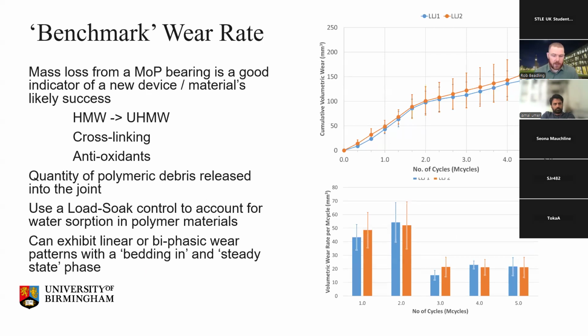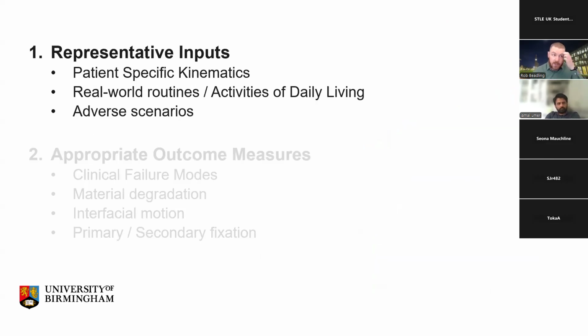And then we see a lot of failure modes that aren't captured in that testing, and then a lot of research goes into trying to understand why that failure happened, as opposed to doing it the other way, where you do the safety or the representative testing to make sure the device is safe beforehand, before it's then implanted into people. So the bulk of my research has been around improving preclinical testing, and that's been through 2 main streams.